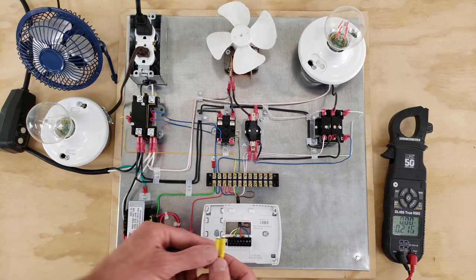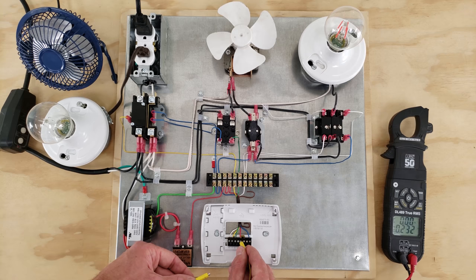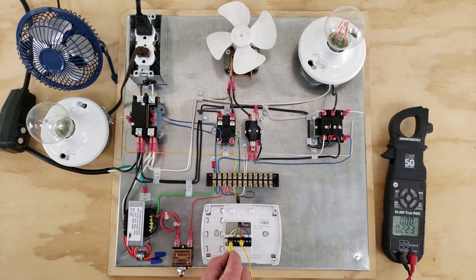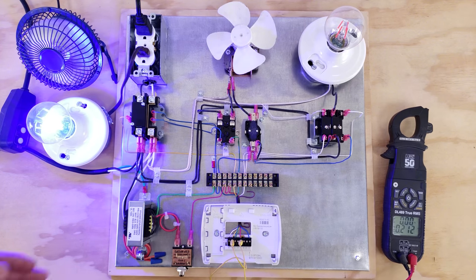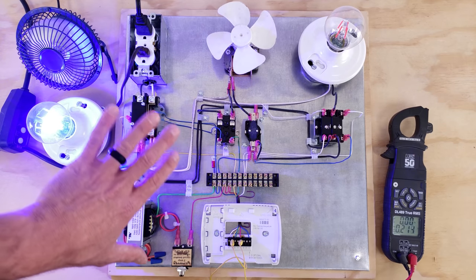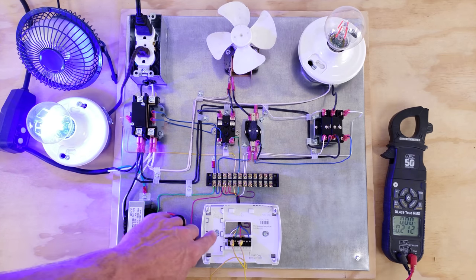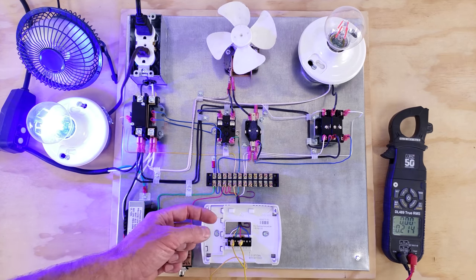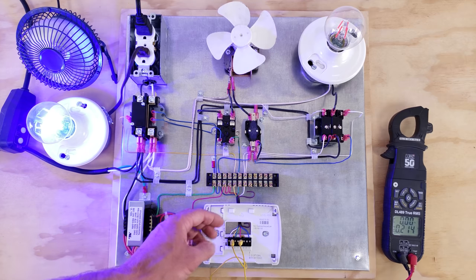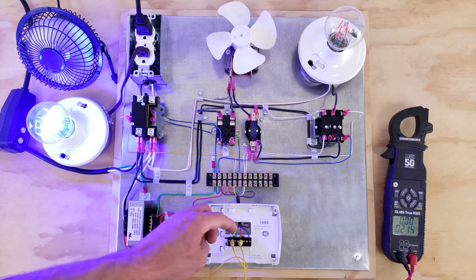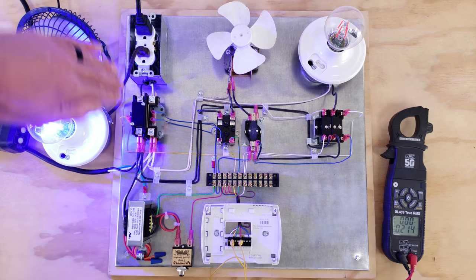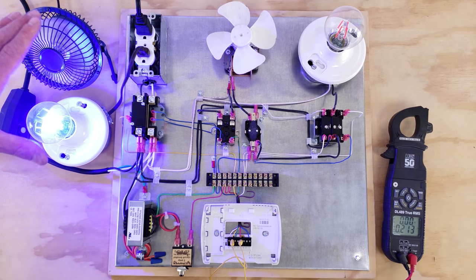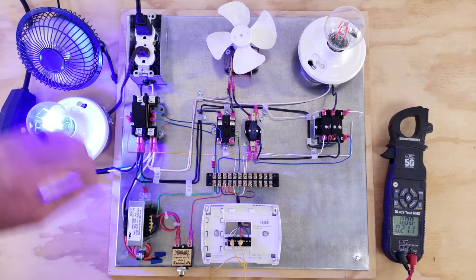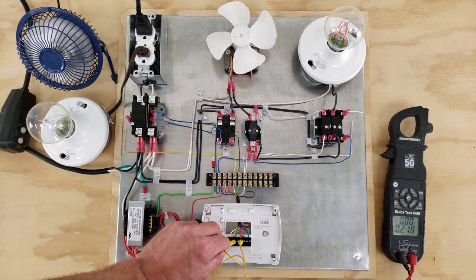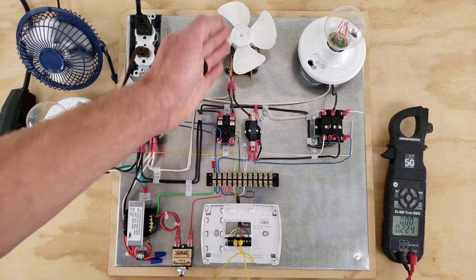And so now we'll use our magnet jumpers to jump from R to Y in order to turn our air conditioning on. Remember that it's not going to turn on our indoor fan anyway. It's just going to turn on our outdoor unit, because your thermostat normally connects R to both G and Y. So since we're just connecting R to Y, it's only going to power this circuit over here for your outdoor air conditioning to turn on. So it seems that our indoor fan is not running.